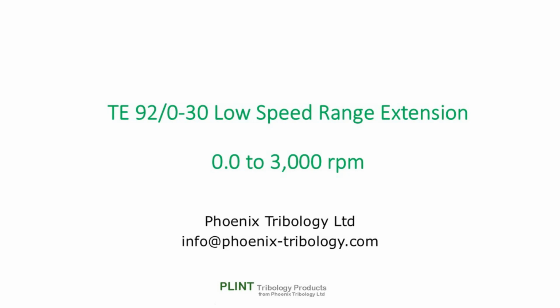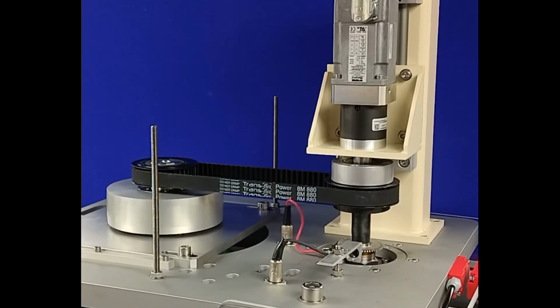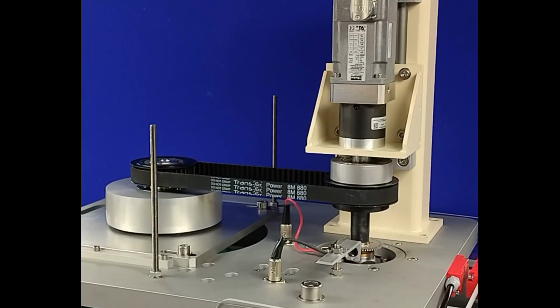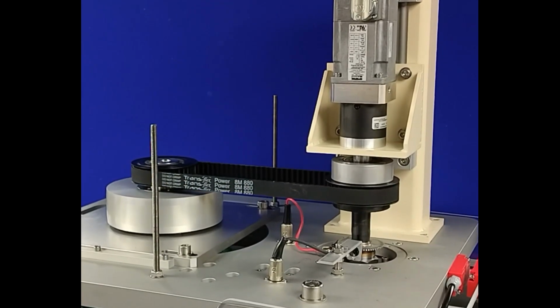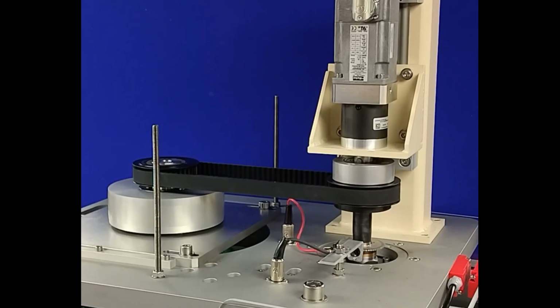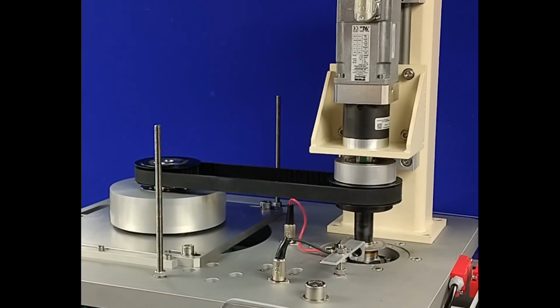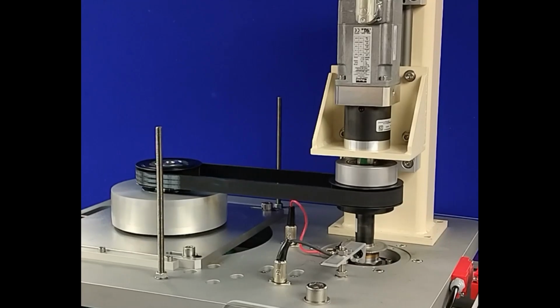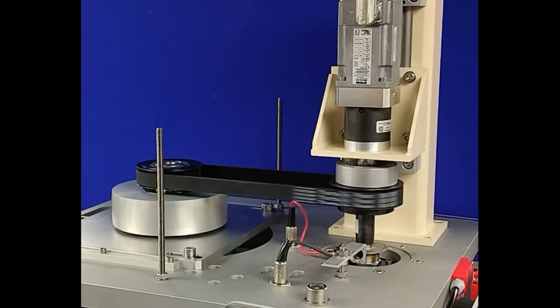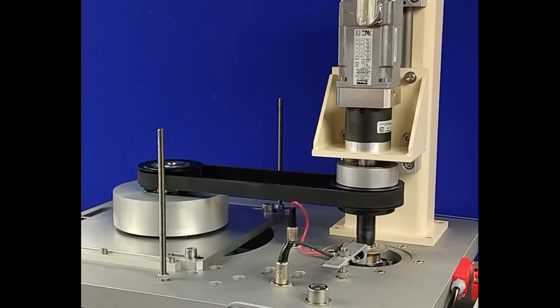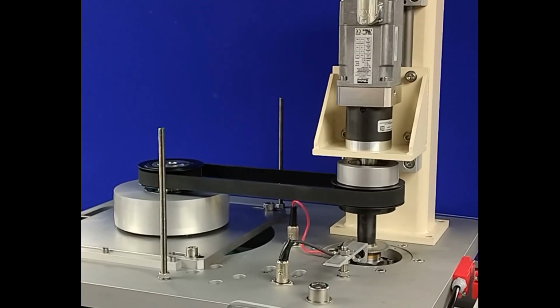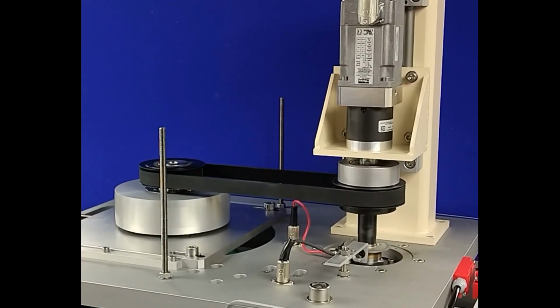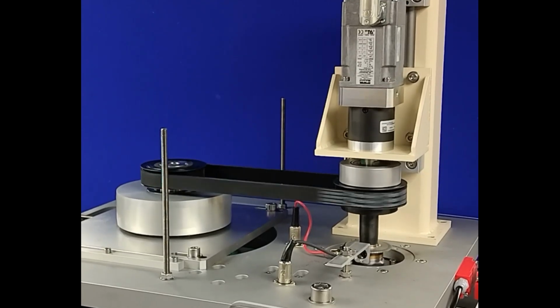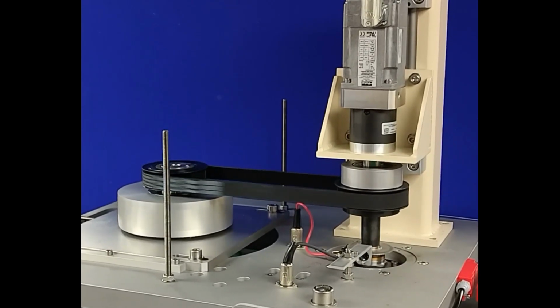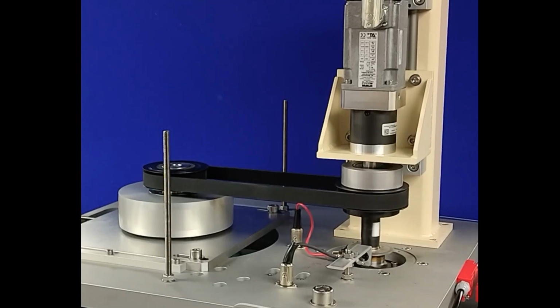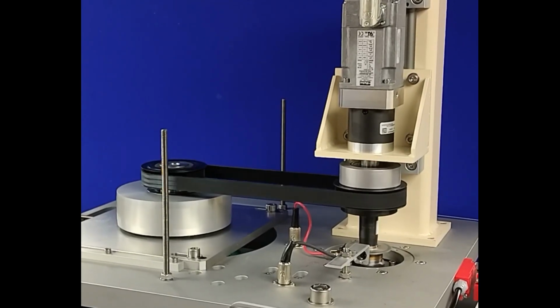Standard motors will not normally run smoothly at very low speeds. To allow precise control of low speed motion with a continuous speed ramp up to, say, 3000 RPM, we have the option of fitting a geared motor in parallel with the normal machine drive motor. This is connected to the machine spindle by a sprag clutch.